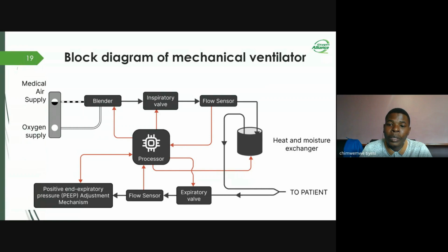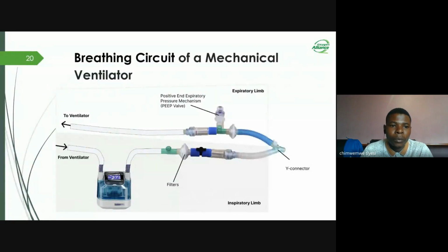So there's also a processor or a microcontroller which receives and sends signals to most of the mentioned parts in the diagram, which regulates key ventilation parameters such as tidal volume, inspiratory rate, and also inspiratory and expiratory times. Apart from these parts, the mechanical ventilator has also other elements like alarms, monitors, and also, of course, an oxygen sensor. So these work together to make sure the ventilator functions properly and the patient gets the right amount of oxygen. Next, I'll talk about the breathing circuit of a mechanical ventilator.